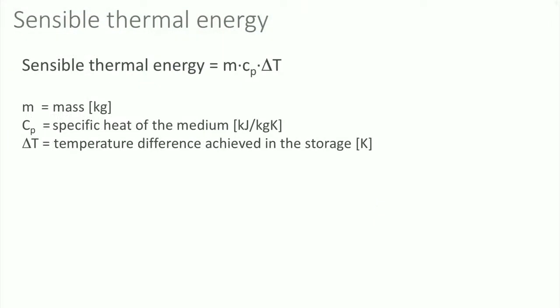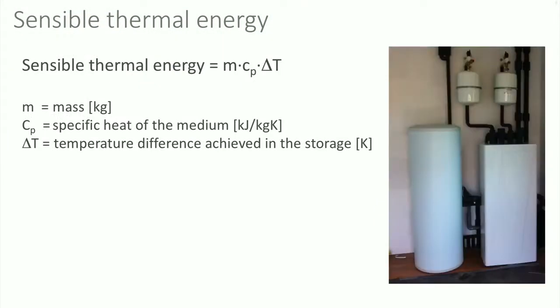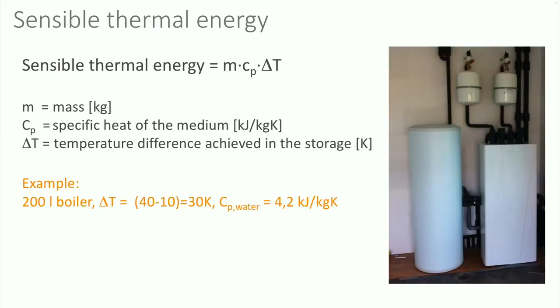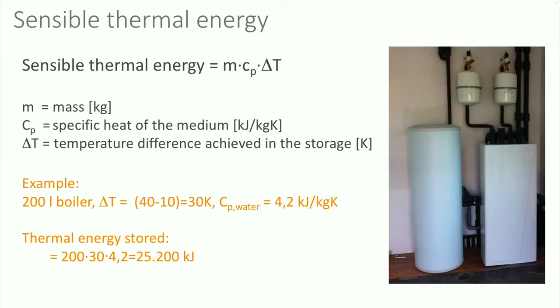As an example, the thermal energy stored in a hot water buffer is shown. The boiler has a volume of 200 liters and the temperature is raised with 30 degrees Celsius. The specific heat capacity of water is 4.2 kJ per kg·K. The thermal energy stored is thus 200 times 30 times 4.2, which equals 25,200 kJ. If you divide this value by 3600, you will get the energy content in the unit kWh, resulting in a value of 7 kWh of thermal energy stored. This is enough for taking 7 showers of 5 minutes.